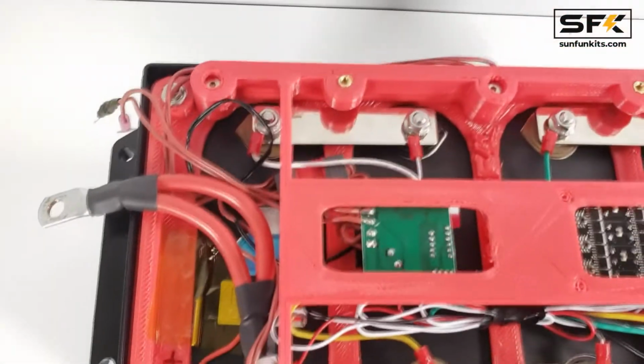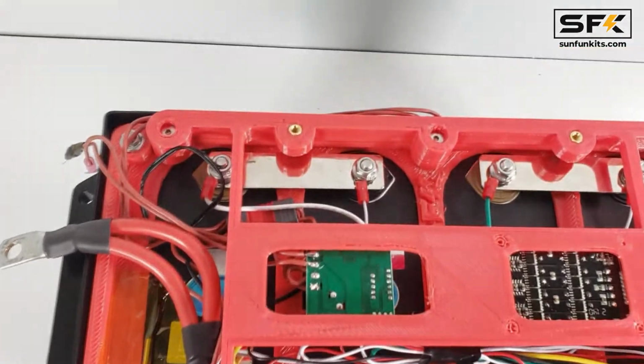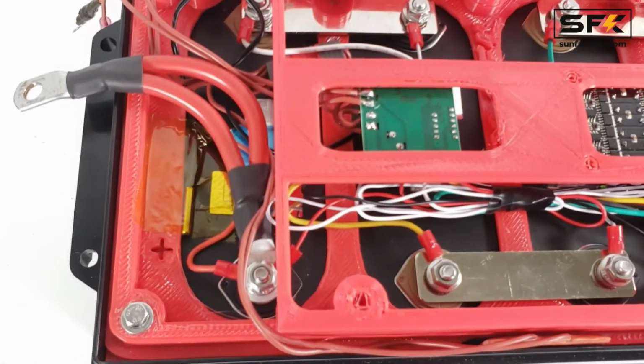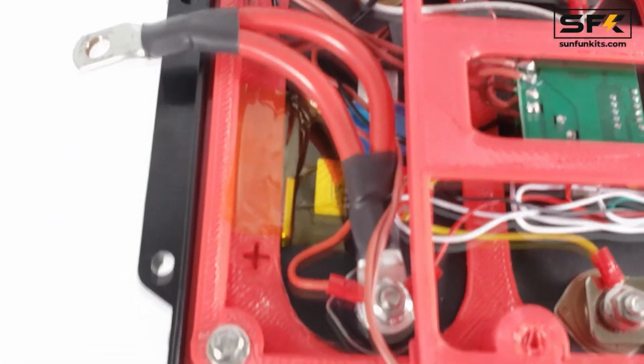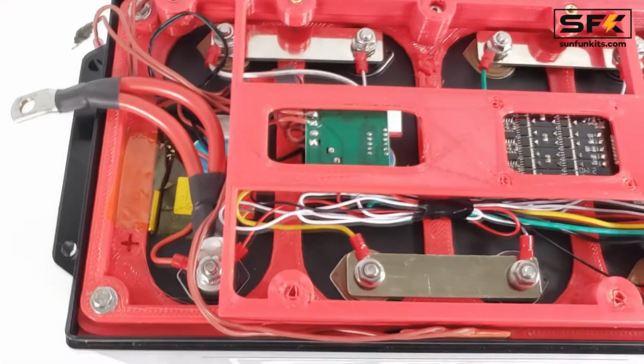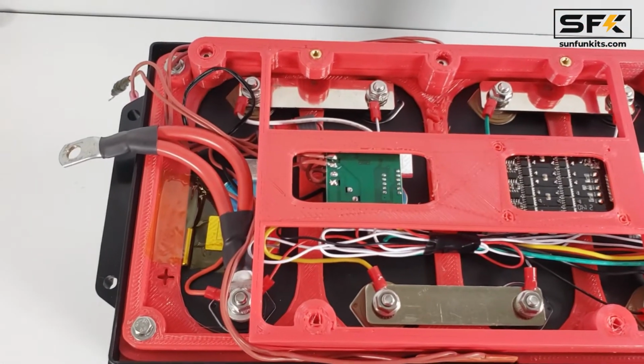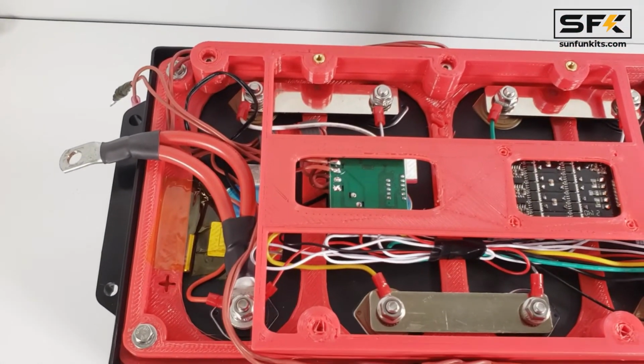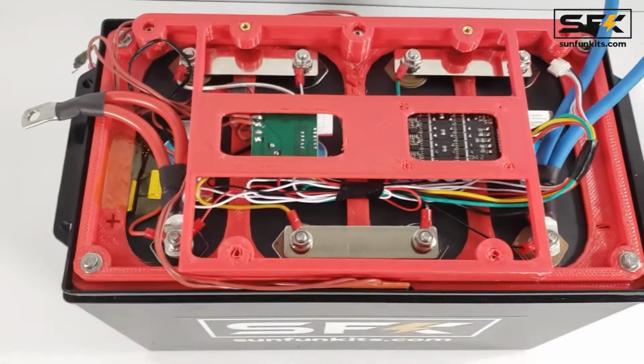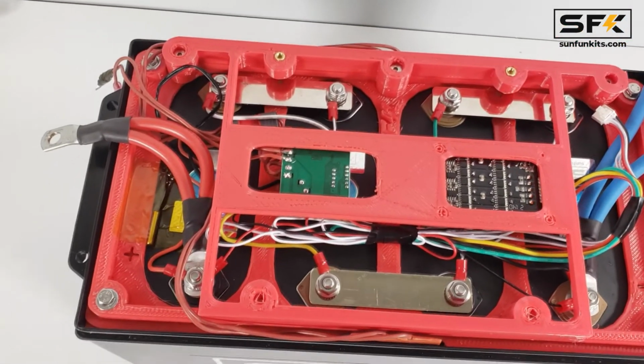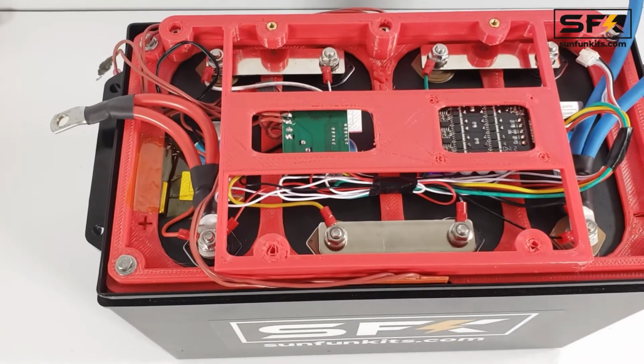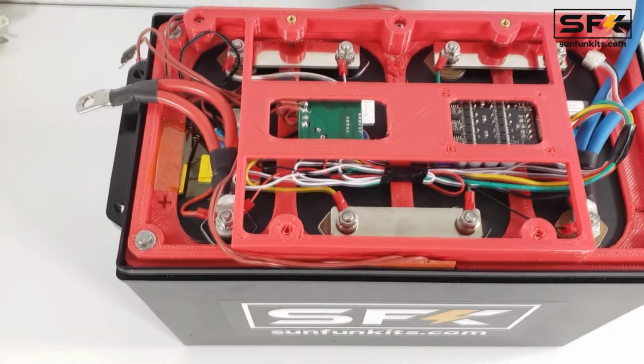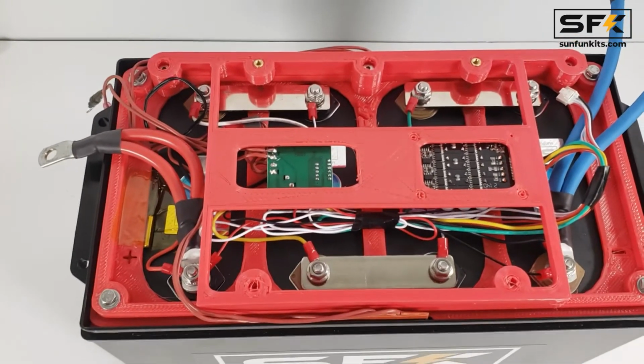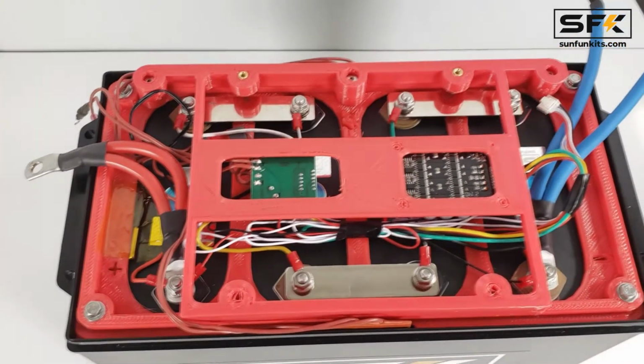We have now attached the silicone heating pads to the main power source from the thermo switch, and we've also attached the thermo probe to one of the cells using Kapton tape. This allows the thermostat to base its reading off the temperature of one of the cells in our kit. If the ambient or cell temperature falls below the threshold, the kit will automatically turn on and bring the battery to the appropriate temperature.